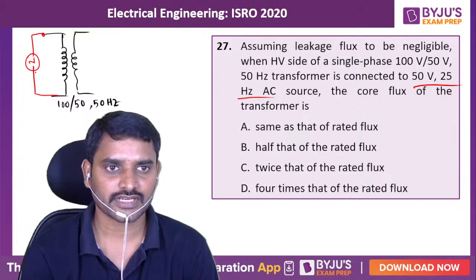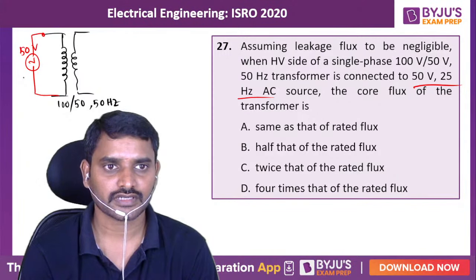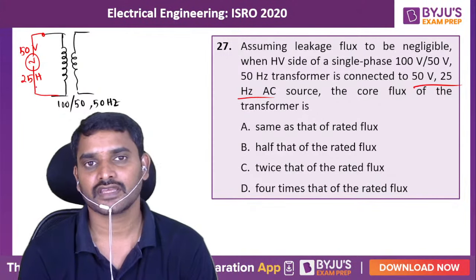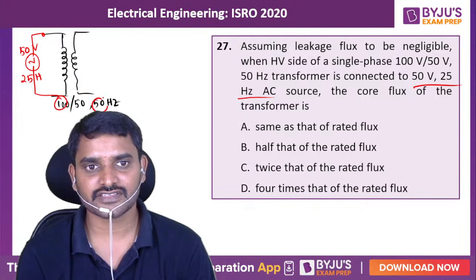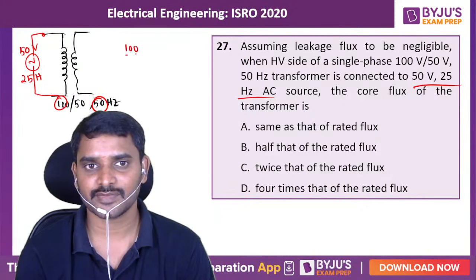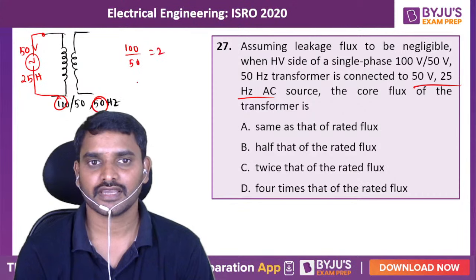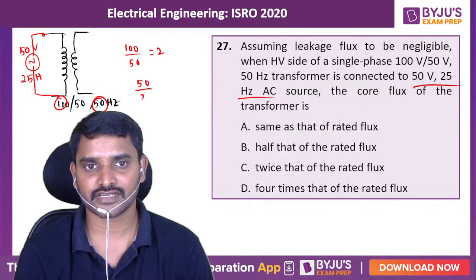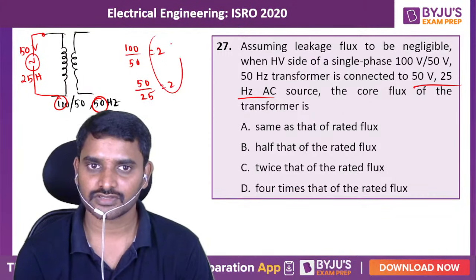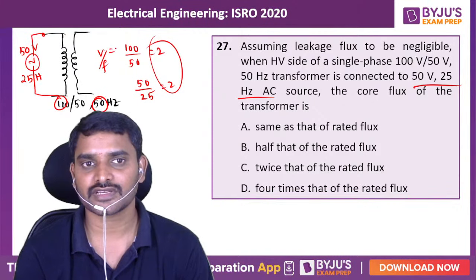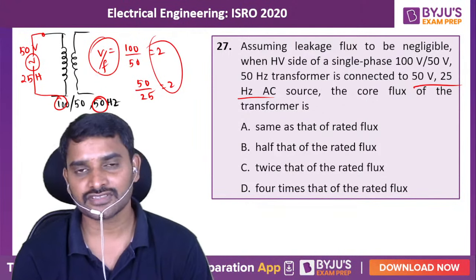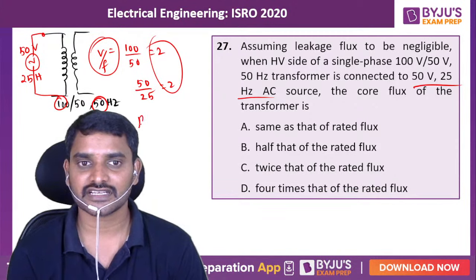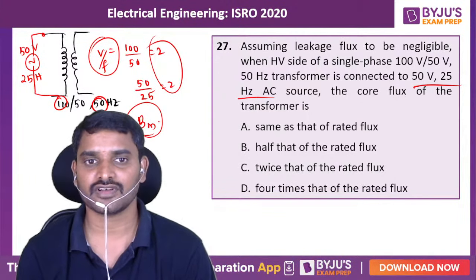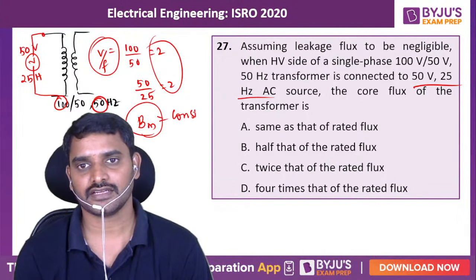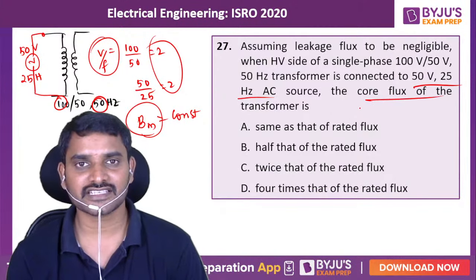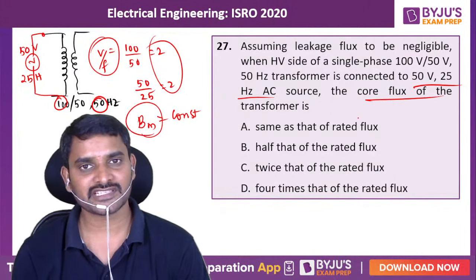So the source voltage is going to be 50 volts 25 hertz. So it's like voltage to frequency ratio. In the first case it is 100 by 50, it is going to be 2. In the second case it is going to be 50 by 25, this is also going to be 2. So the voltage to frequency ratio is going to be constant. If the voltage to frequency ratio is constant, then the flux density establishment is also going to be constant. So he is asking about core flux establishment. Will it be the same or different?